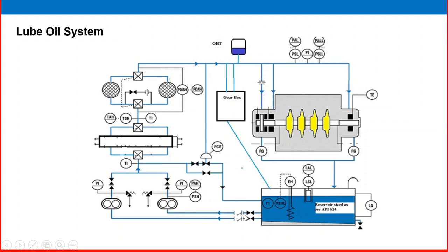This is a simple diagram of the lube oil system. The lube oil reservoir, or tank, feeds the running and standby pumps. It is then connected to a filter and cooler system to keep the lube oil clean and at the correct low temperature. The oil enters the compressor, gearbox, and other moving parts — going through each section and returning to the reservoir after completing its service cycle.